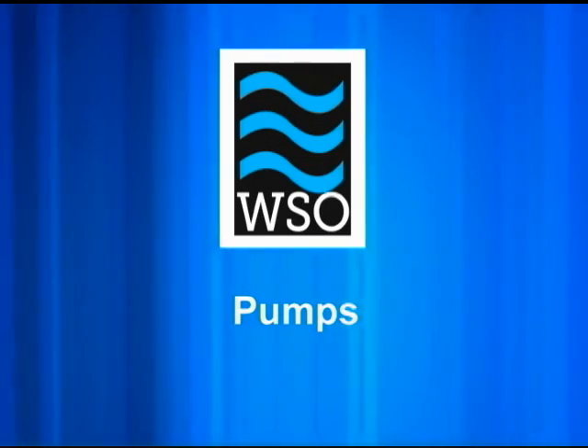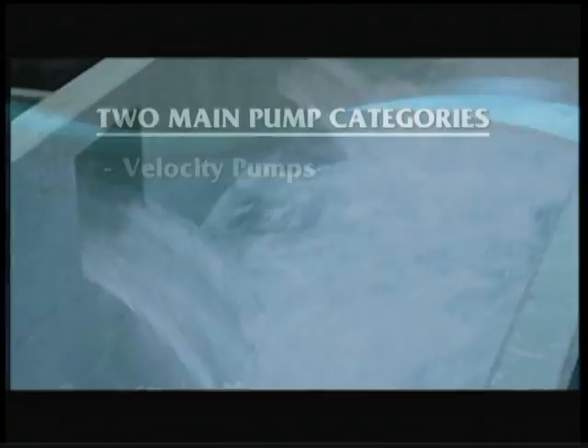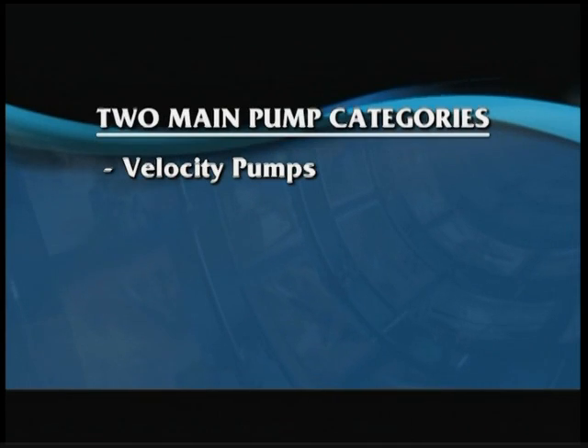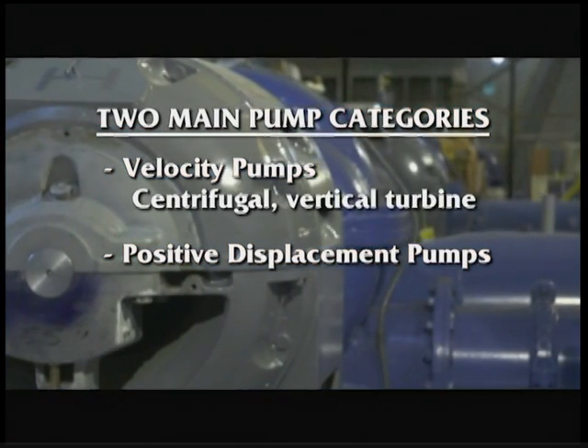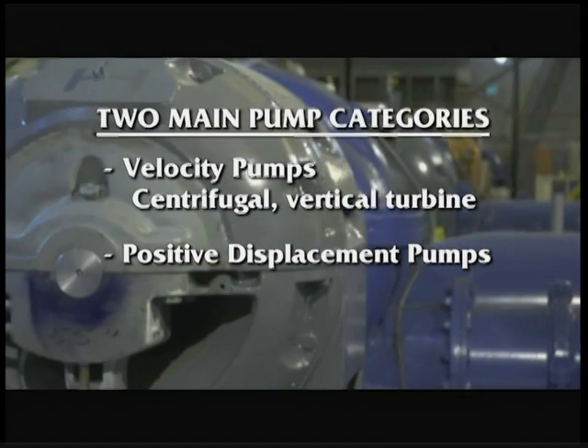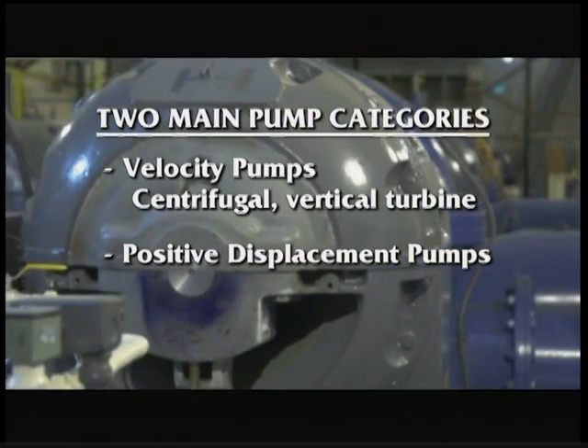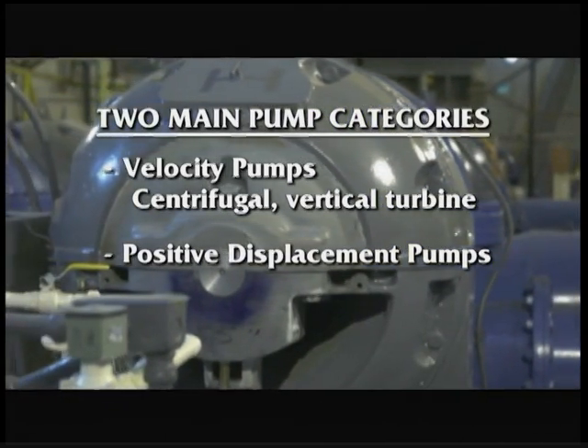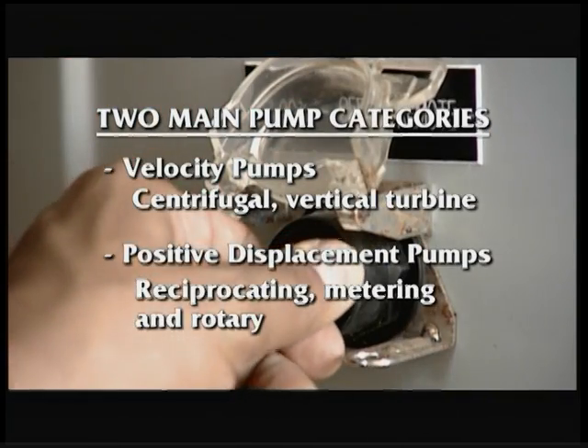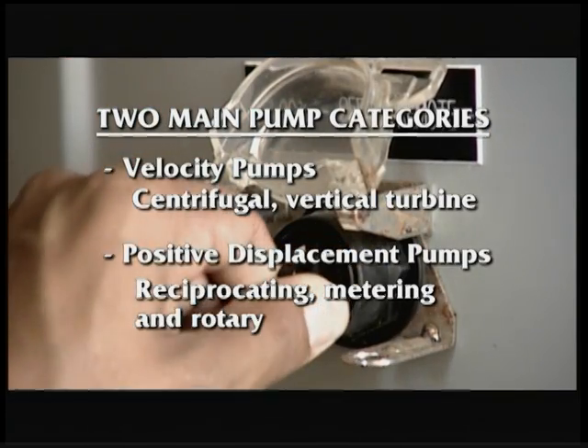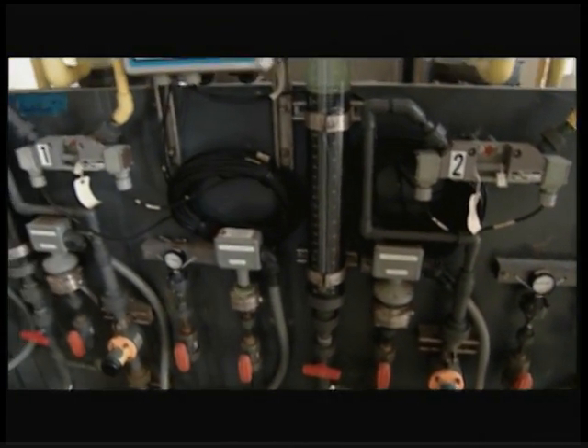The two main categories of pumps used in water supply are velocity pumps and positive displacement pumps. Velocity pumps, including centrifugal and vertical turbine, are used for most distribution system applications. Positive displacement pumps, including reciprocating and rotary, are used for moving abrasive or harmful materials and metering chemical feed systems.